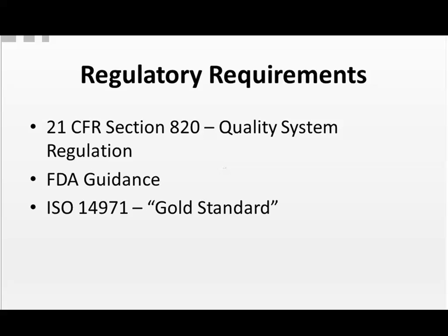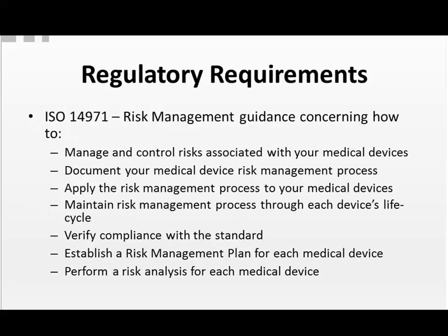It addresses the application of risk management to medical devices and establishes a risk management standard to be applied to medical devices. The ISO document helps manufacturers identify risk and develop, implement, and monitor the effectiveness of their control measures. Now, the ISO document is most precisely a regulatory document concerning risk analysis for medical devices, as I've said. The standard addresses risk management for patients, operators, other parties, other external equipment, and/or the environment.